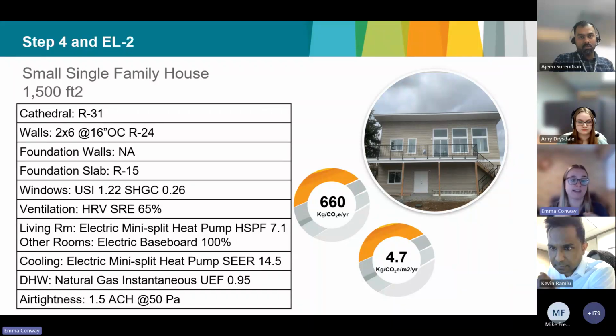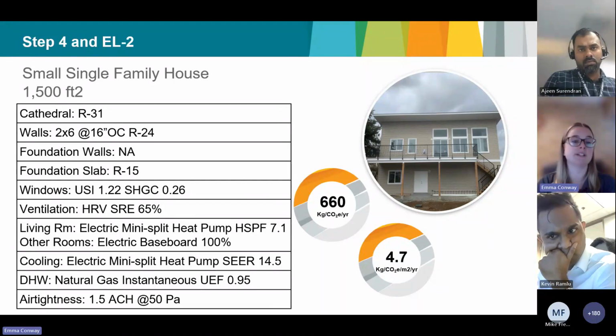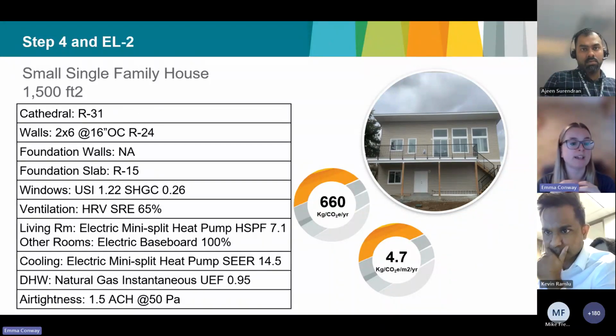For my mechanical, I did add an HRV, and I went all electric baseboard because this is a small home - it doesn't have a large heating load. Does it make sense to put a forced air system in this little home? No, it doesn't. So I did 100% electric baseboard with the exception of the living room, where I added a mini split, not only for energy efficiency but also for the cooling requirement - at least one room in the home has to have cooling.